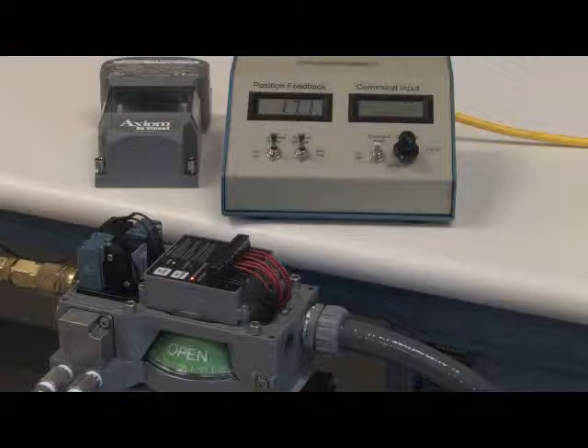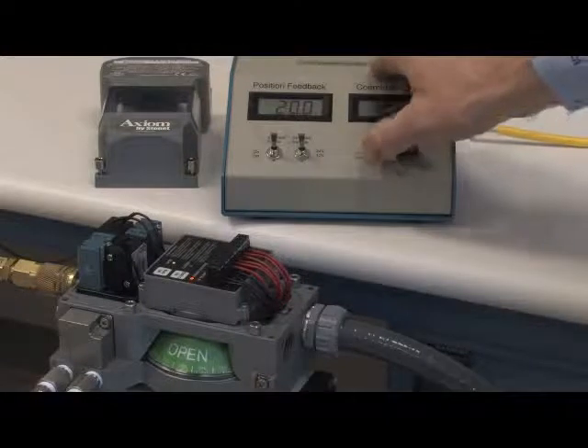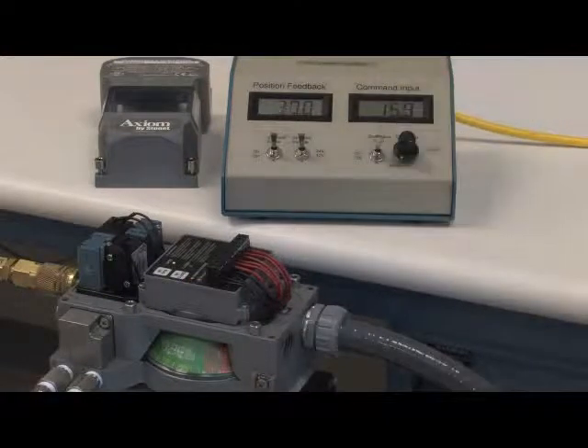We'll energize the main power. We're full open at 20 milliamps. When we energize the command input, it'll go to 16 milliamps.